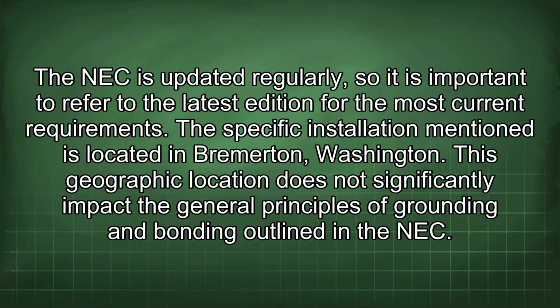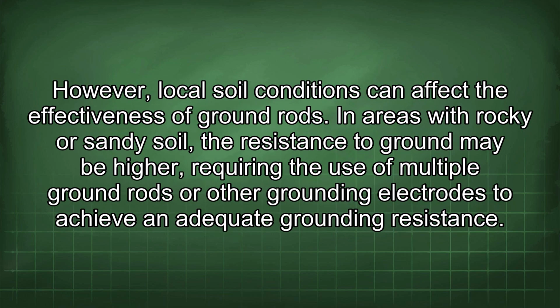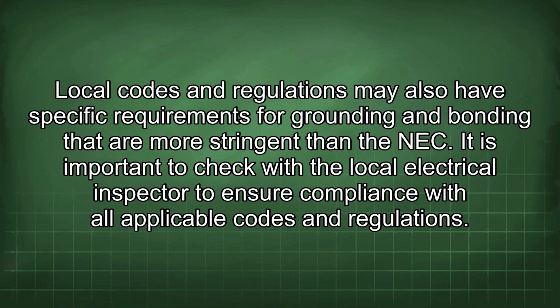The specific installation mentioned is located in Bremerton, Washington. This geographic location does not significantly impact the general principles of grounding and bonding outlined in the NEC. However, local soil conditions can affect the effectiveness of ground rods. In areas with rocky or sandy soil, the resistance to ground may be higher, requiring the use of multiple ground rods or other grounding electrodes to achieve an adequate grounding resistance. Local codes and regulations may also have specific requirements for grounding and bonding that are more stringent than the NEC. It is important to check with the local electrical inspector to ensure compliance with all applicable codes and regulations.